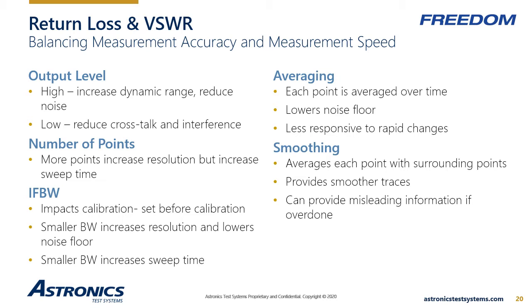Averaging lowers the noise by time averaging each sweep point with the same point in previous sweeps. The longer the averaging count, the less responsive the trace will be to sudden changes in level. So, keep this in mind, as this could be detrimental when looking for intermittent issues.